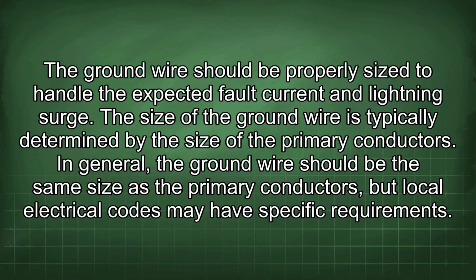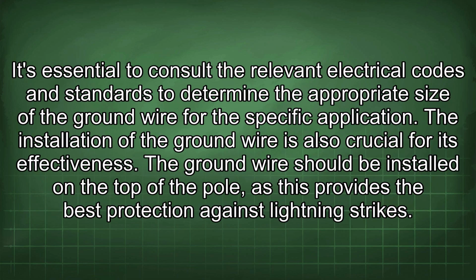The ground wire should be properly sized to handle the expected fault current and lightning surge. The size of the ground wire is typically determined by the size of the primary conductors. In general, the ground wire should be the same size as the primary conductors, but local electrical codes may have specific requirements. It's essential to consult the relevant electrical codes and standards to determine the appropriate size of the ground wire for the specific application.